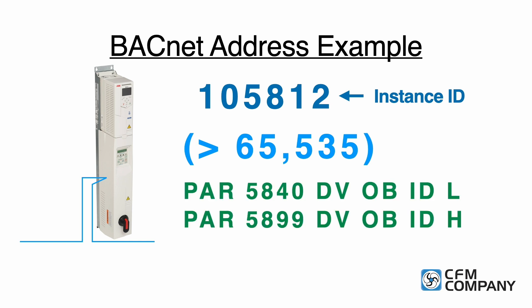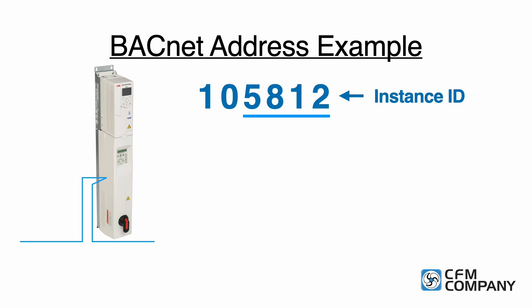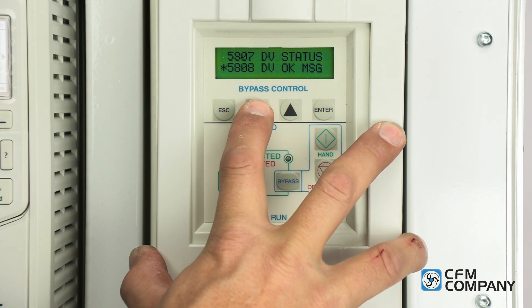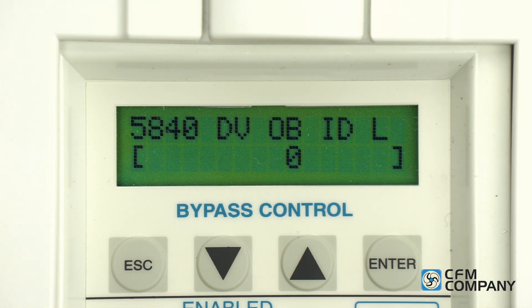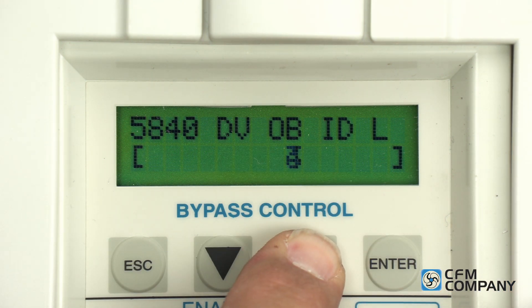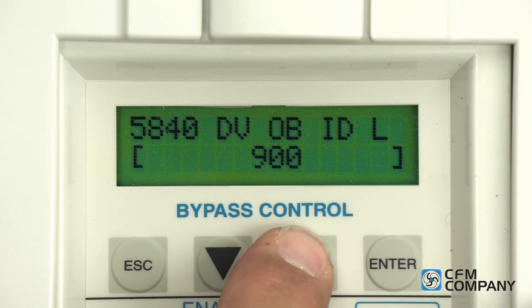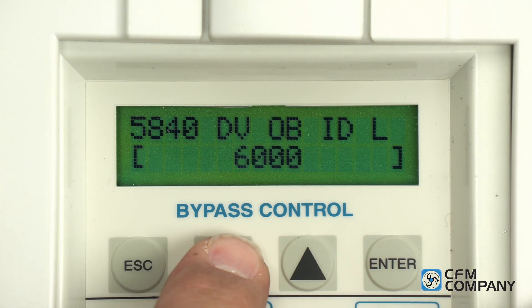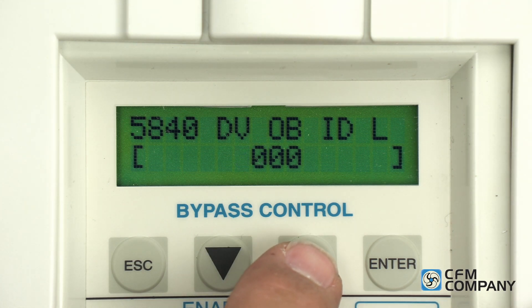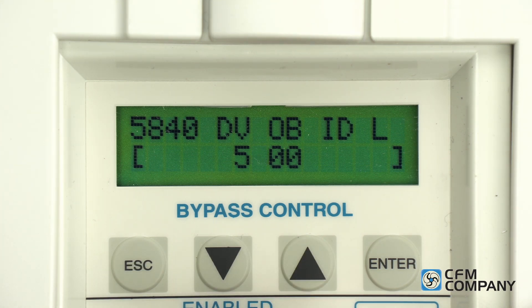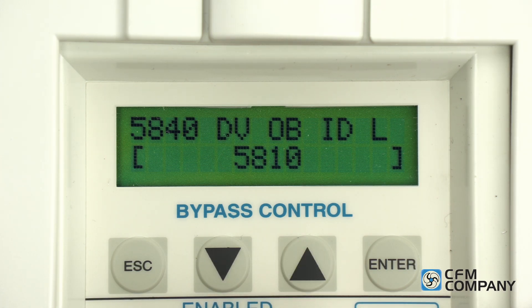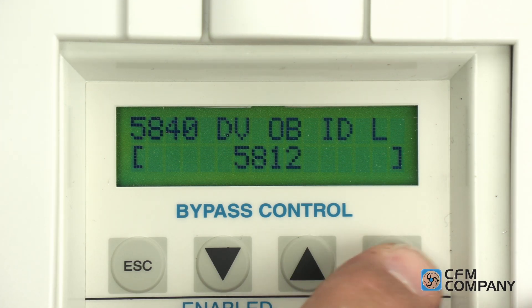Splitting the number into two parts is easy. First, use the four digits from the right. In our example, these are digits 5, 8, 1, and 2. On the Eclipse control panel, navigate to parameter 5840 dvobidl and press enter to edit the value. Use the up arrow to increase the value. Holding the up arrow longer will shift the cursor from ones to tens to hundreds to thousands place. Waiting or releasing the arrow will cause the cursor to shift back down. Once the correct value of 5812 is entered, press enter to save.